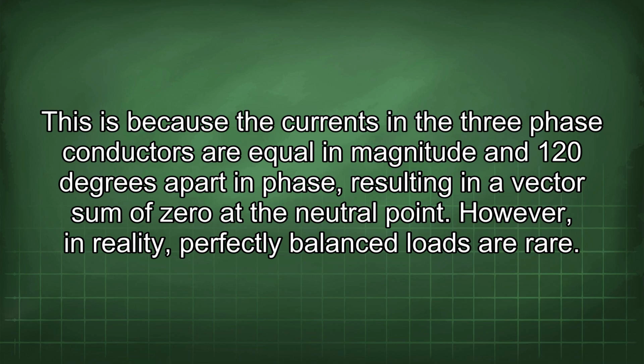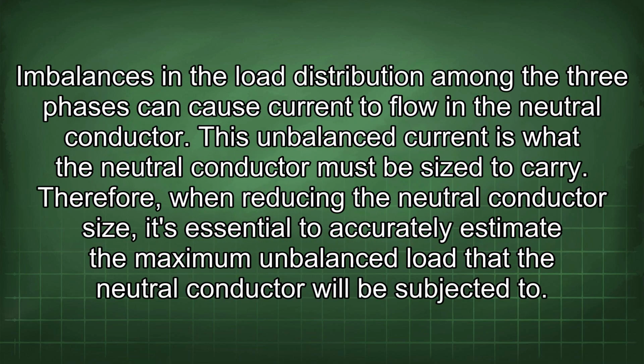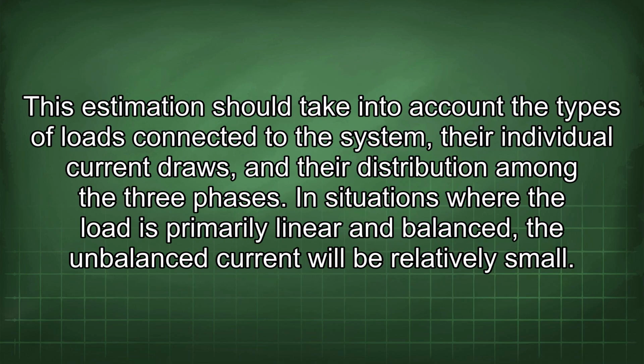However, in reality, perfectly balanced loads are rare. Imbalances in the load distribution among the three phases can cause current to flow in the neutral conductor. This unbalanced current is what the neutral conductor must be sized to carry. Therefore, when reducing the neutral conductor size, it's essential to accurately estimate the maximum unbalanced load that the neutral conductor will be subjected to. This estimation should take into account the types of loads connected to the system, their individual current draws, and their distribution among the three phases.